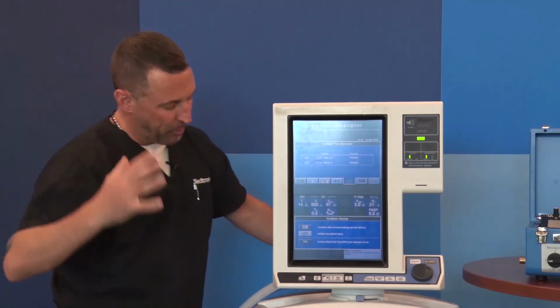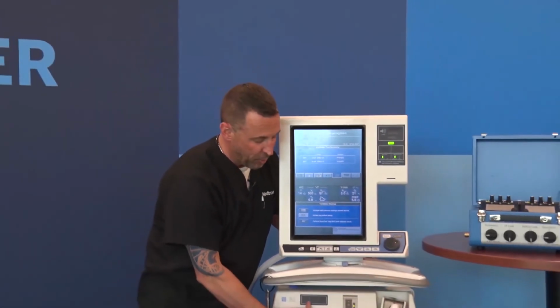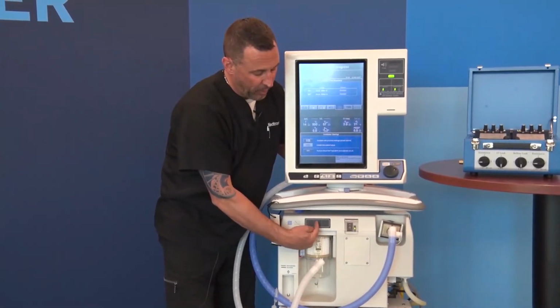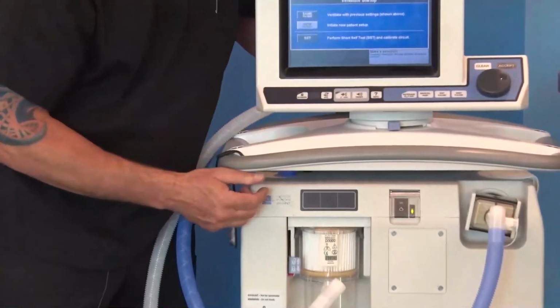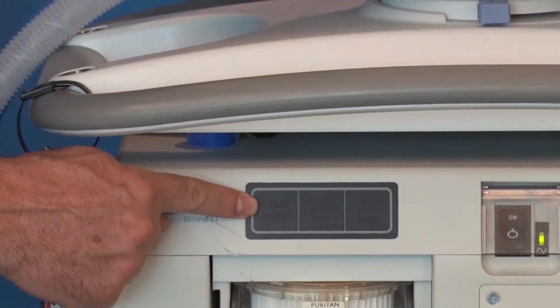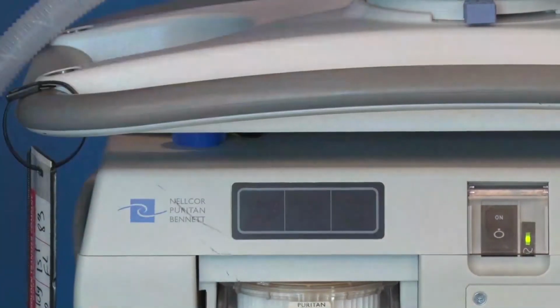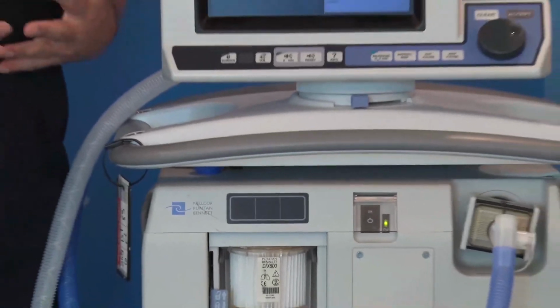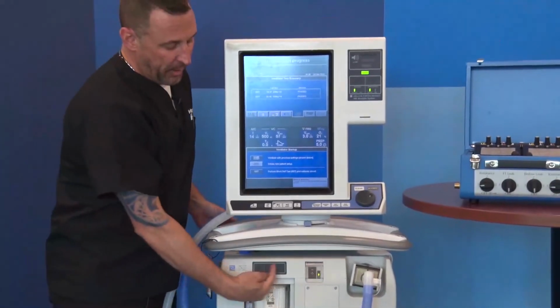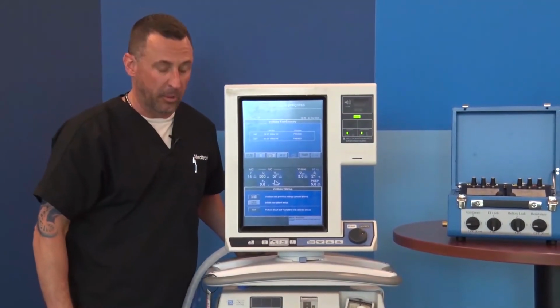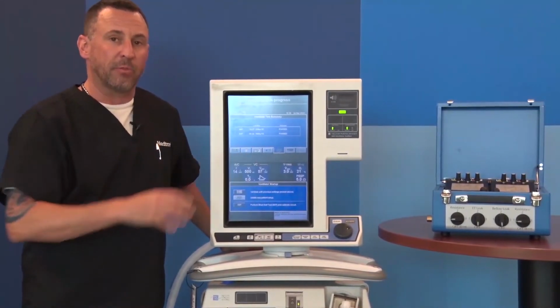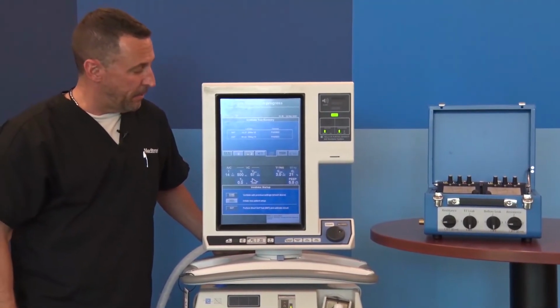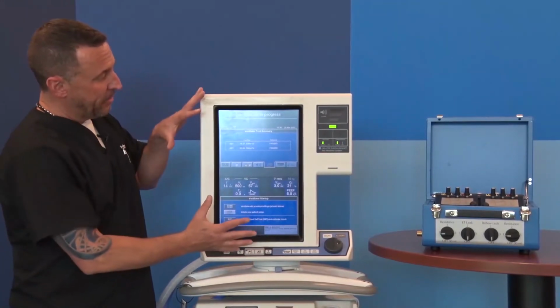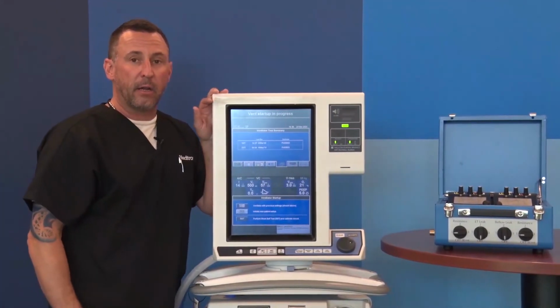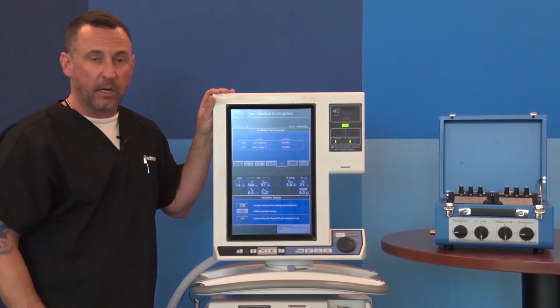One last note on the ventilator itself from a macro perspective. There are 3 alarms or visual indicators of alarms that if one of these comes on, those are very serious alarms. You have an unrecoverable event, such as a vent inop or a safety valve open, or something about the GUI's communication with the ventilator has been interrupted. So a really loud high pitch accompanied by a light here, your ventilator is inop and you're going to be switching vents. We have other alarms for patient conditions, and I'll certainly go over that in more detail. So let's kind of attack the screen, start identifying what's on here, and in short order we'll have you ventilating something here in just a minute.